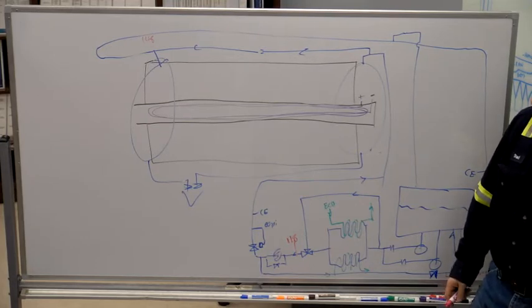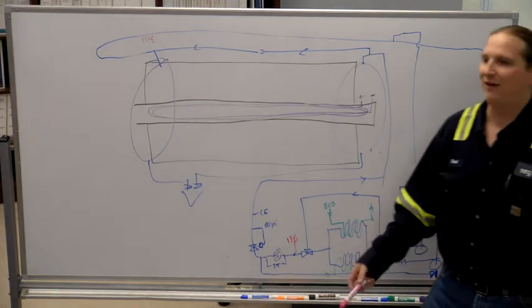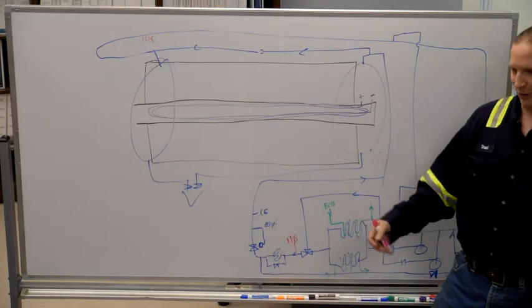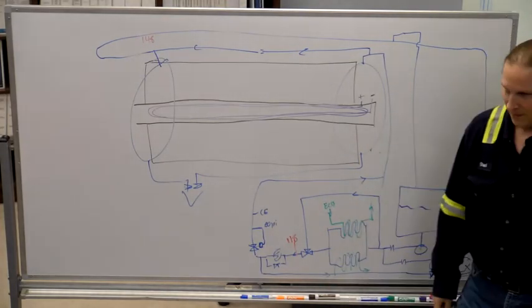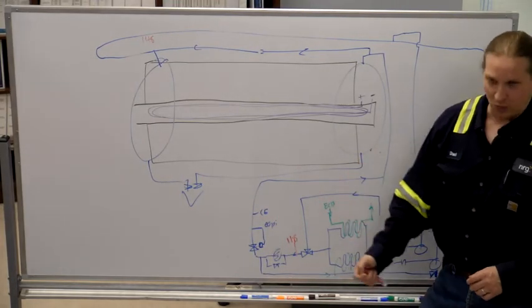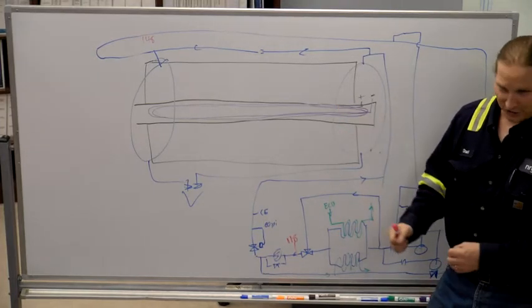So most of us know hydrogen is explosive, it's flammable. Most flammable things are also explosive in the right circumstances. So if you have normal air and there is 4% hydrogen, that hydrogen will burn. And then it gets up to 12% hydrogen, and that hydrogen will explode.